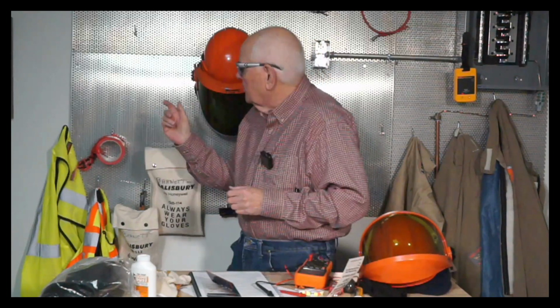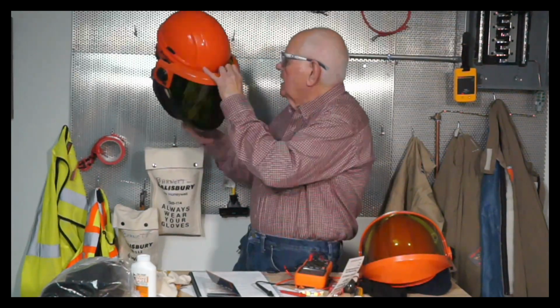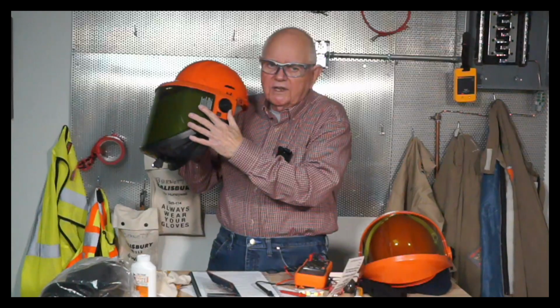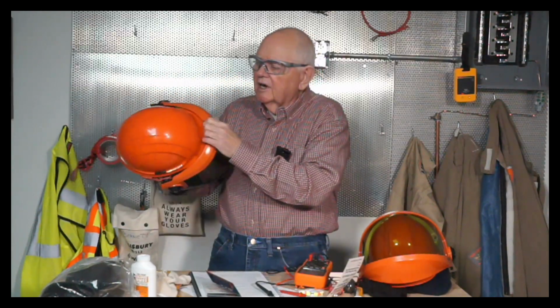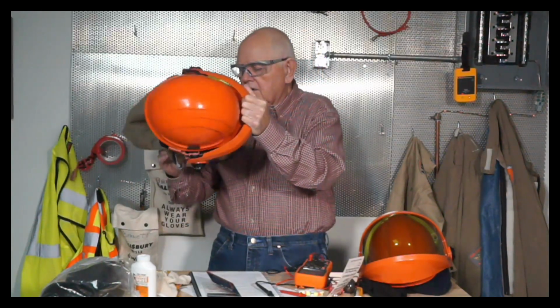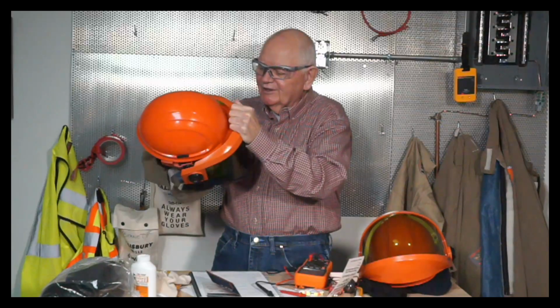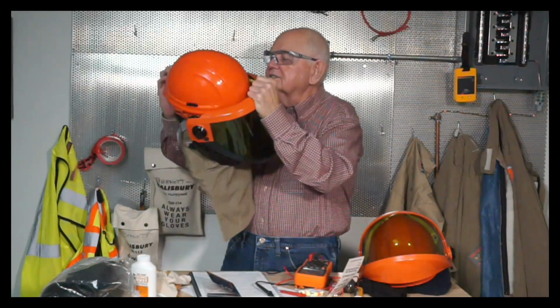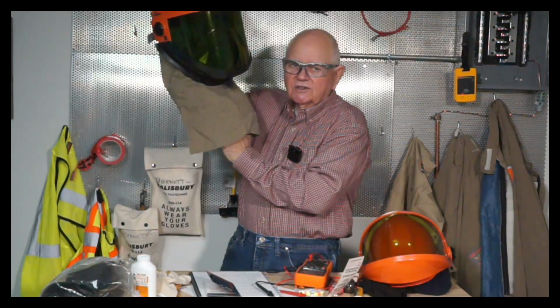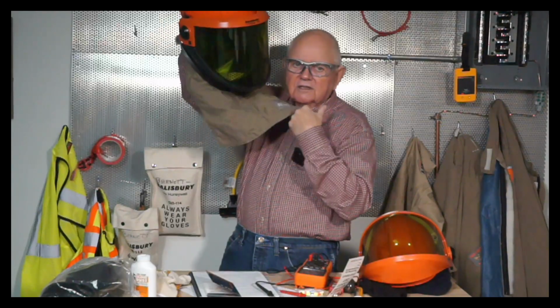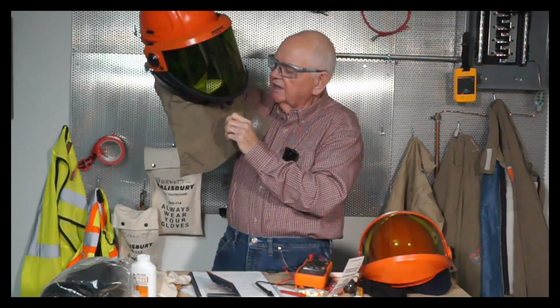Here's another type of face shield. This is a good one. This one is rated for 40 calories, so it's good for up to 40 calories per square centimeter of arc flash energy. And it's got the hood built into it, so when I put it on, it just falls down over my chest.